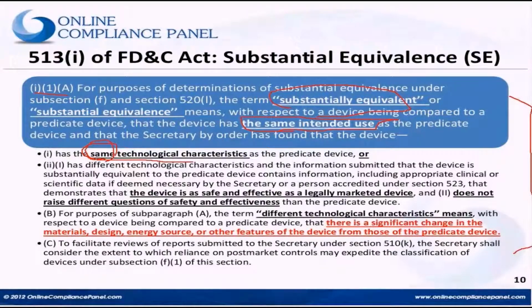And what if the device does not have the same technological characteristics? Well, you have to show that your device is still safe and effective, and we are going to talk about that further. For example, let's look at here. Your subject device has the same intended use and the same technological characteristics, and therefore your device is as safe and effective as a legally marketed device.